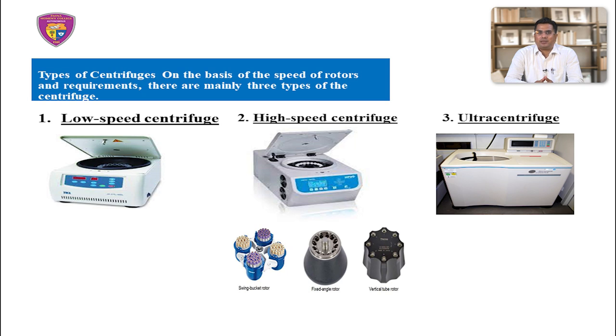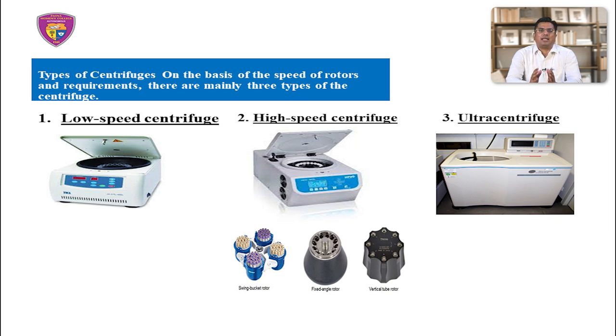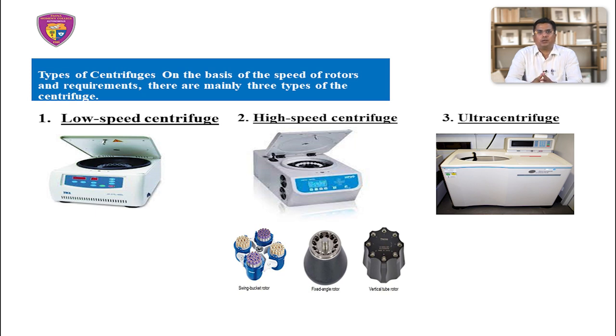The third type is the ultracentrifuge, the most sophisticated instrument, with a maximum speed of 65,000 RPM. Since intense heat is generated at ultra-high speeds, the spinning rotor chamber must be refrigerated and kept at a high vacuum. It is used for both preparative and analytical work, meaning isolation and analysis. According to applicability, categories include micro centrifuge, small bench-top centrifuge, general purpose centrifuge, and large capacity centrifuge.